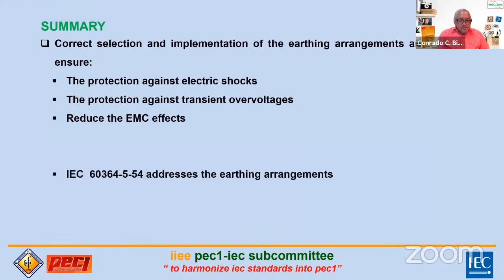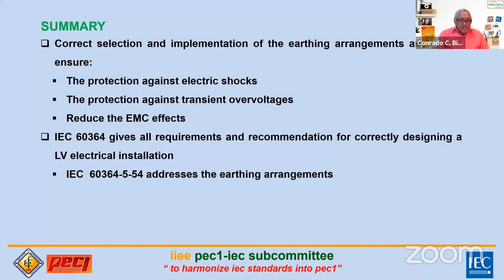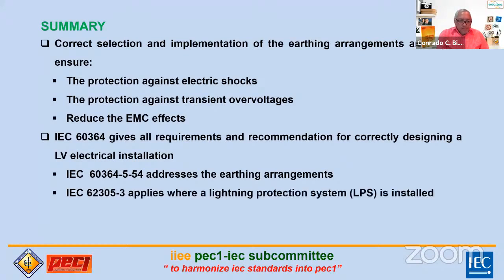Then this one, the IEC 60364-5-54, addresses the earthing arrangement. Then we have here for designing electrical installation, kailangan mo itong 60364 para ma-design mo properly yung earthing arrangement. And of course, you have to consider IEC 62305-3, which applies when a lightning protection system is installed. So kailangan mo yan, sa IEC, ito yung mga ginagamit na standards.